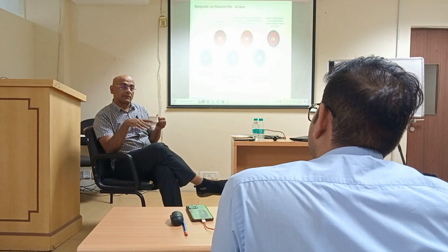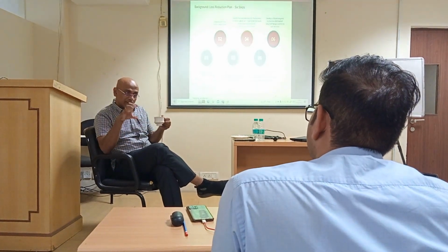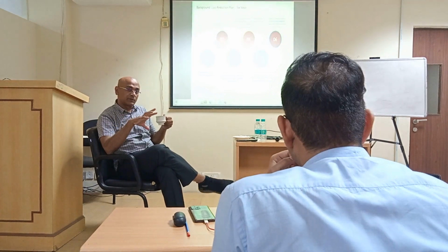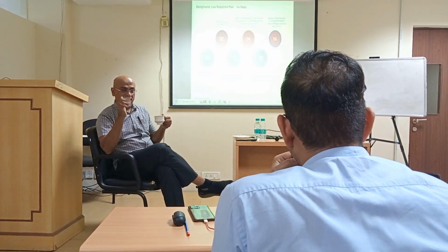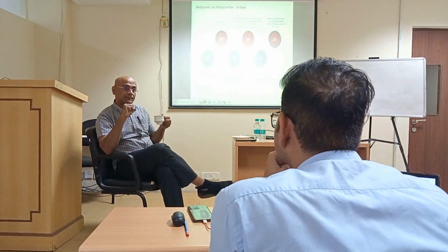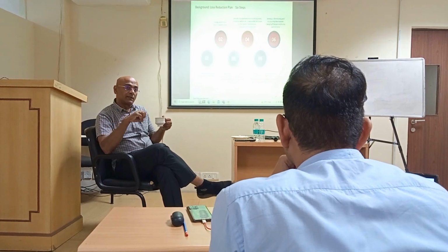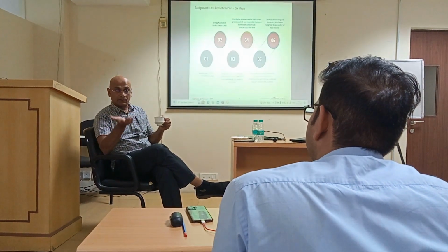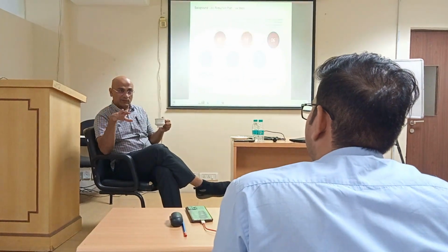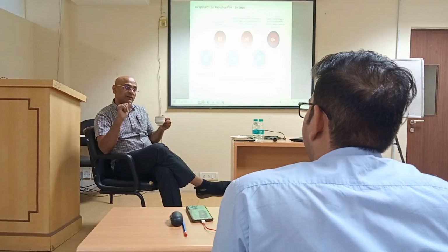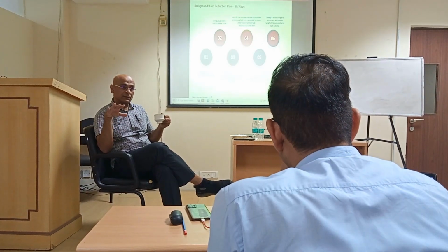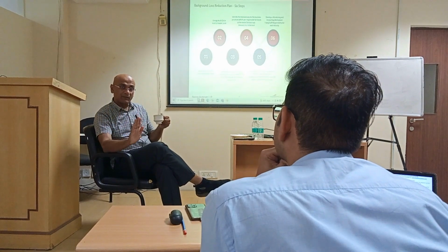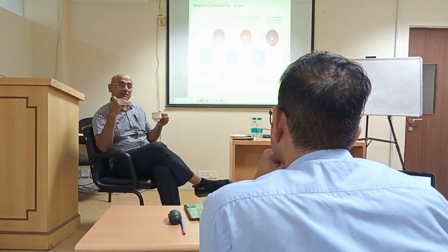Then we did the implementation. So we have those intervention exercises. I'll just tell you in 1 minute about the implementation experience we had. There is a place called Rajgangpur in Odisha. It was near Rourkela. You must have heard of that. That was an industrial belt. So we did 100% metering of all those industries and then did the meter reading through MRIs. But in those days AMR or smart meters were not there. So with MRI reading, in just 2 to 3 months, and the only focus being that we streamlined the energy audit process, in 3 months the losses came down from 77% to 37%.